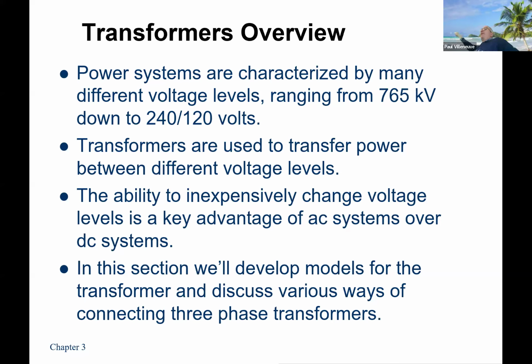So if you were going to have a fault to ground at 7,200 volts, the return path on the other side is distinct from what you would have in your house. So it's not like you would touch the 7,200 and touch a wire in your house and you get electrocuted. You shouldn't get electrocuted. If you touch ground, it would be a different story, but that's the return path for it. So that's the primary reason why we use transformers from a utility perspective. Obviously, it steps down the voltage to much more manageable levels, but we don't want 7,200 volts going into our house. Nothing anywhere close to that.